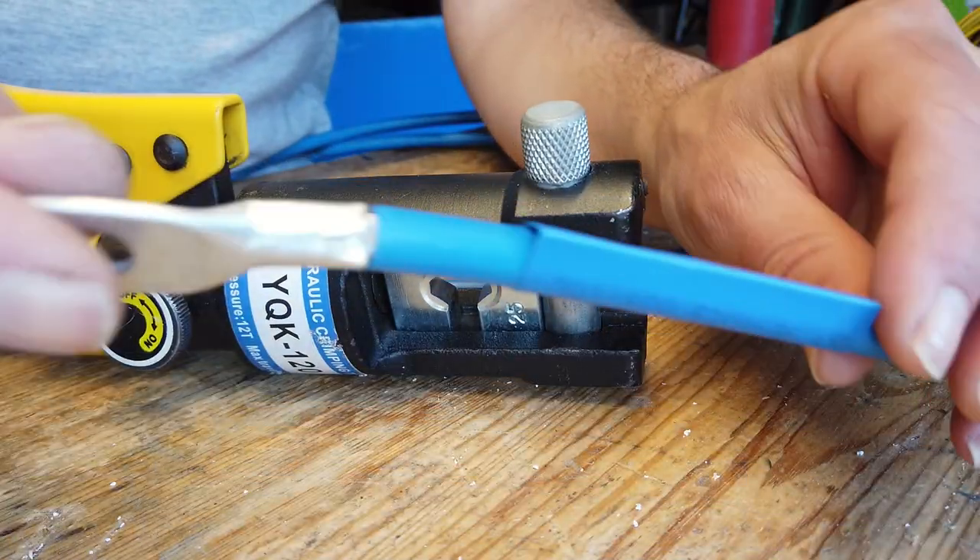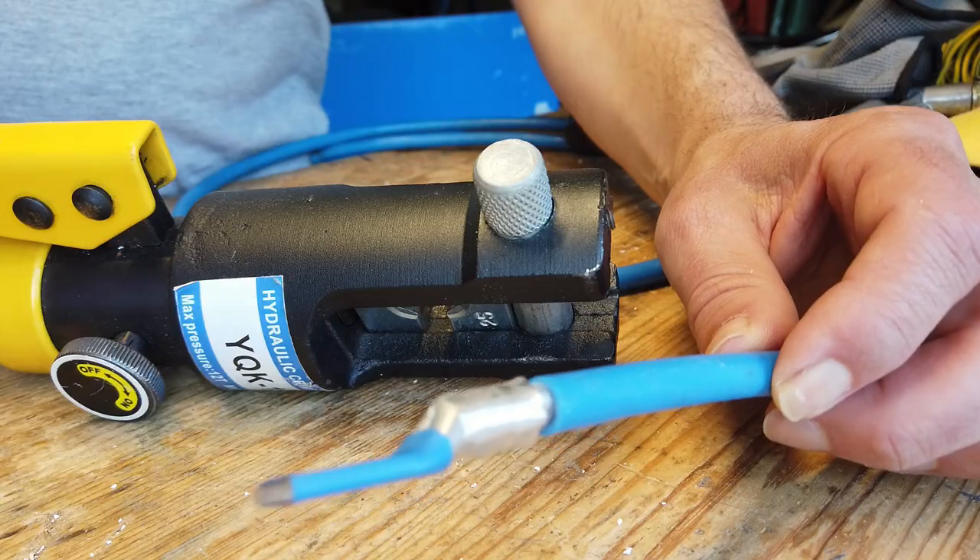So the first one will be crimped with this tool, 25 square millimeter. It's not needed or recommended, but I always apply two crimps in the connector. Above 25 then you should use two. At 25 you're a bit in the gray zone. Number one, so this is the result. I added some shrink tube.